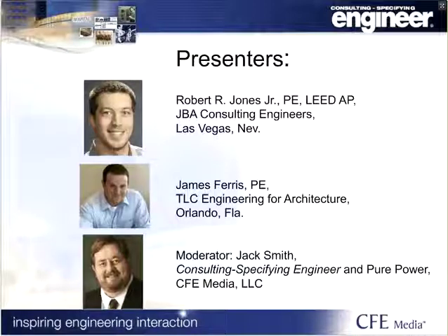Thanks, Jim. Rob, can you shed some light on legally required systems? It's not something you want to do, but the code actually requires it in 700.4(B) in the NEC. Basically, the code requires you to size your generator based on all of the connected loads on the emergency system, but it allows you to account for all of the loads that are intended to operate at the same time on the legally required system.